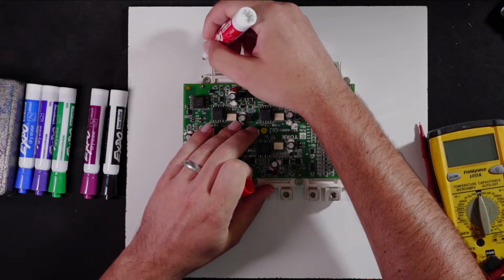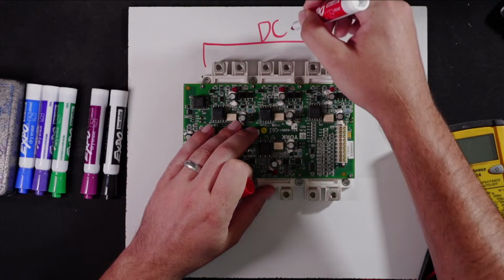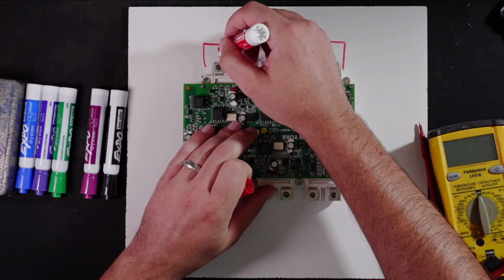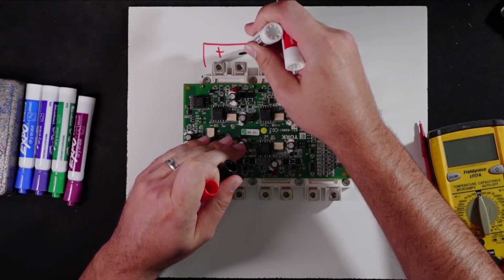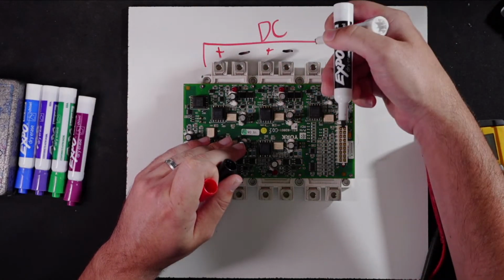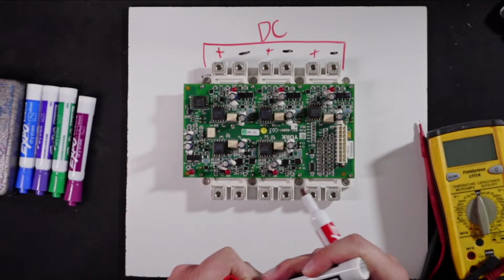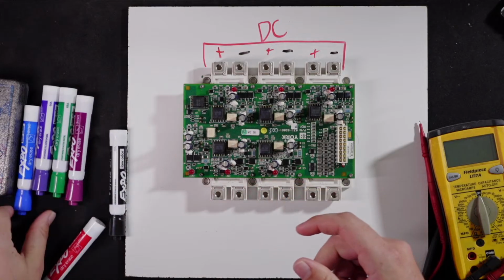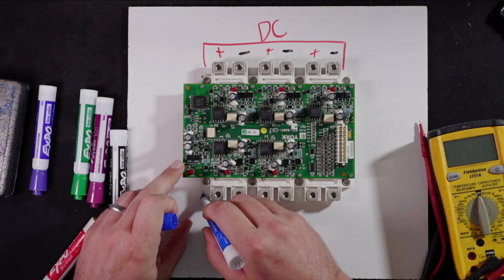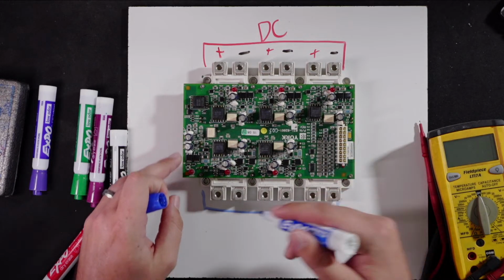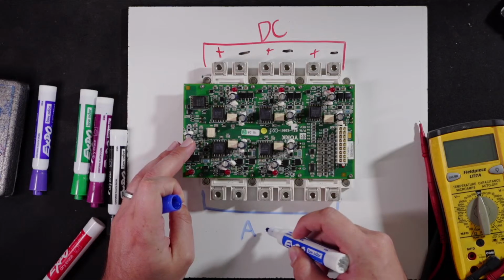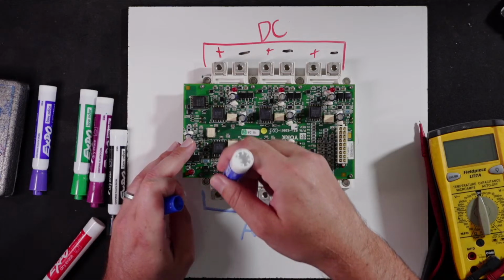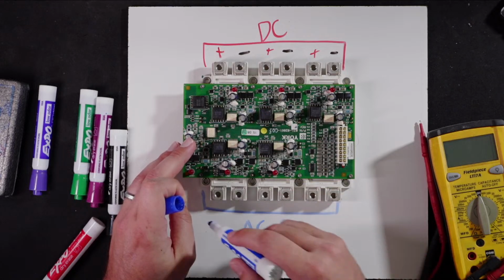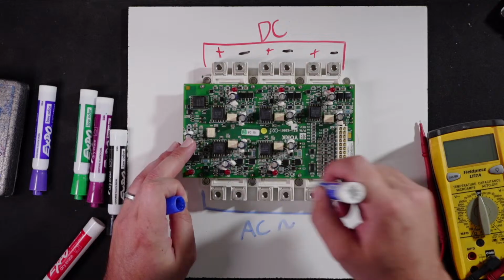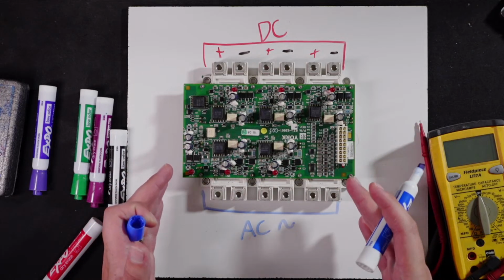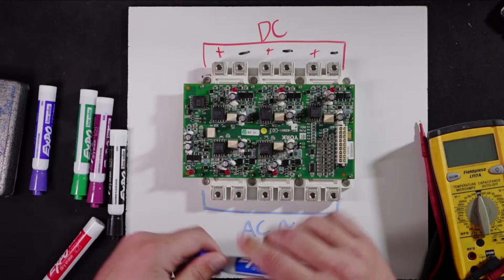Now this is a PWM, so we have our DC bus, and this is going to be our positive and our negative, and then positive and negative, positive and negative. On the output side is going to be our AC. So all of these are going to feed into the AC. Now, depending on the configuration, this could be a single leg, so we could have L1, L2, L3, or there could be a bus bar across here making all of this just one leg of power, and then we would have multiples of these modules in there. So this is just one configuration.